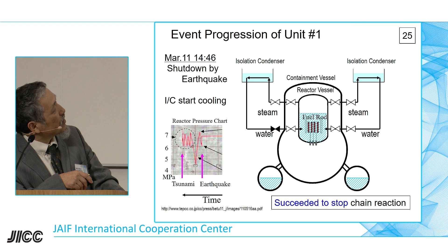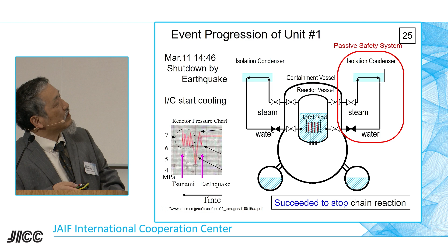I mean, the passive safety system was in a non-operating condition when the tsunami hit it. This is the closed condition. So this is certainly a passive safety system, but if this valve is not open, the passive safety system doesn't work. So even though we have a passive safety system, it should operate not manually, not with electricity, but automatically during the accident condition. Passive safety systems are very important when looking at the Unit 1 systems. Because the tsunami hit and there was no electricity, they could not open these valves. Unfortunately, the system exists, but it did not operate.